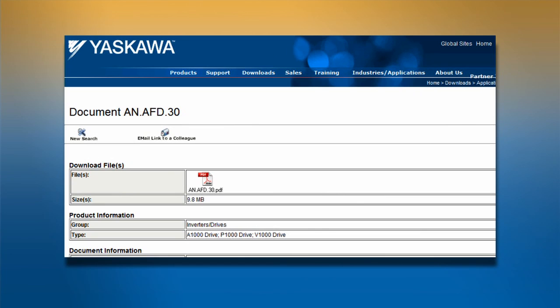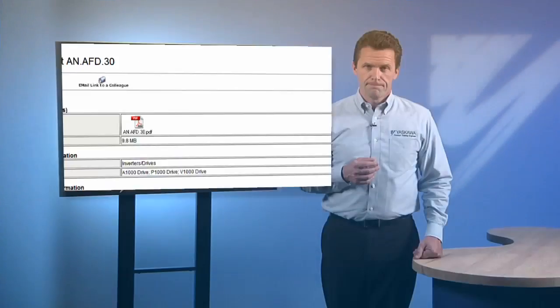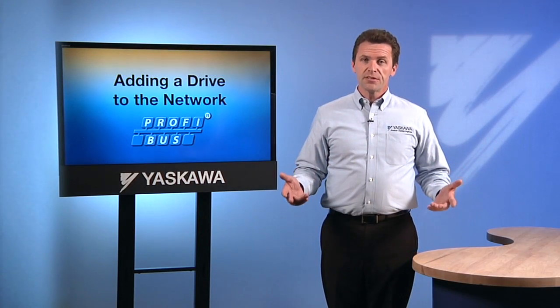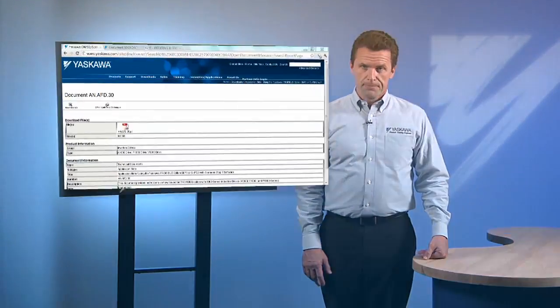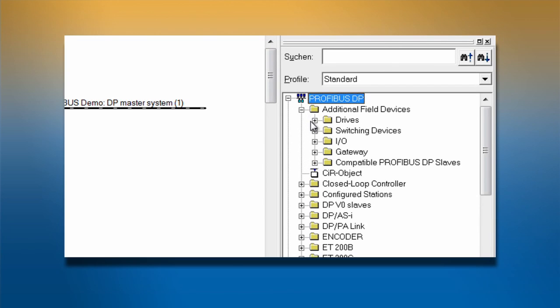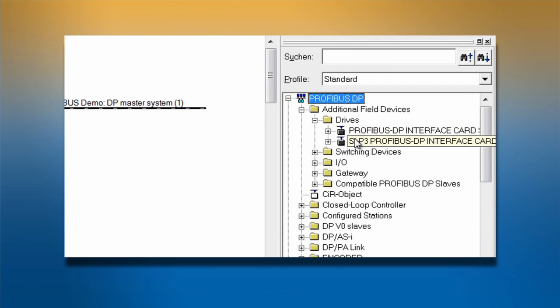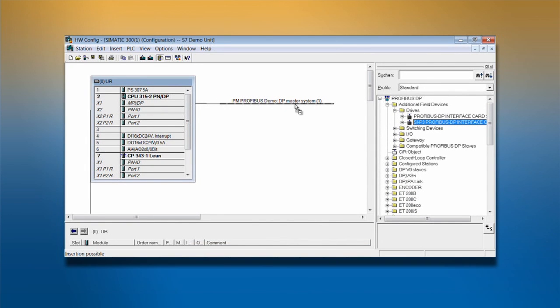Since this process falls outside the scope of this discussion, we won't cover it here. For details on accomplishing this step, refer to document AN.AFD.30 on the Yaskawa website. So once the master is configured, we will need to add your drive as its slave. Select SNP3 PROFIBUS-DP interface card from the list of potential slaves. Click on the slave you wish to add, then drag it onto the network configuration to add it to the network.